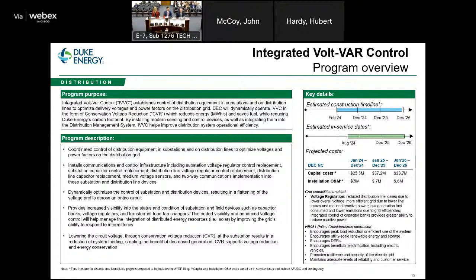Regulators and capacitors, both inside the substation as well as out on the distribution lines, are deployed. New capacitors and regulators are installed if needed. We upgrade the controls for existing installations as well, and bring communications back to the control centers. That's how we integrate that into the distribution management system to operate the system more efficiently.